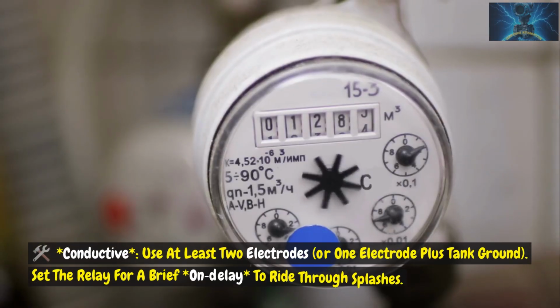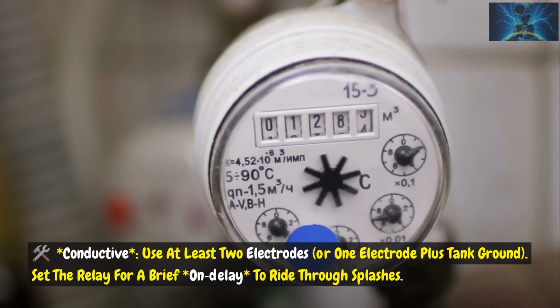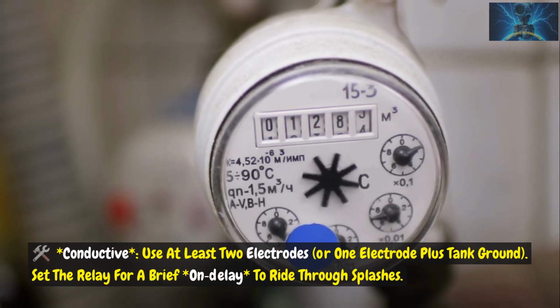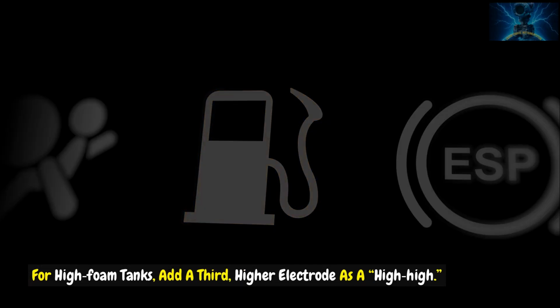Conductive: use at least 2 electrodes, or 1 electrode plus tank ground. Set the relay for a brief on delay to ride through splashes. For high foam tanks, add a 3rd higher electrode as a "high-high."